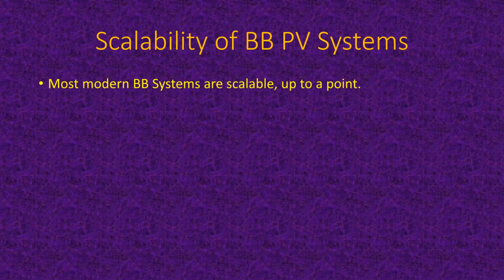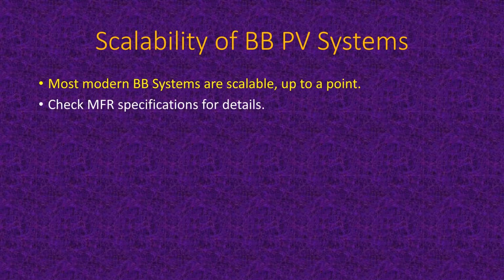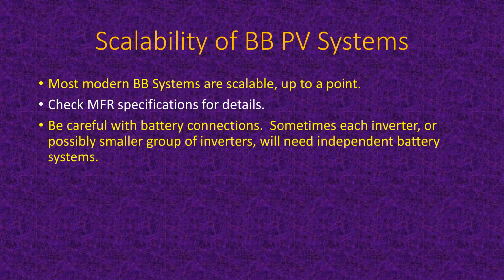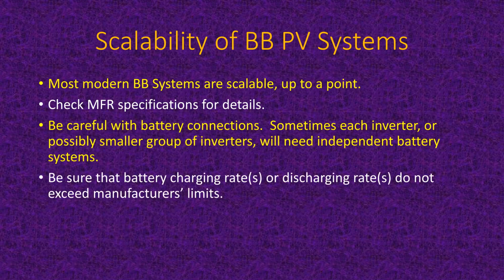Scalability. Generally, you can scale these things up. You got, say, an 8 kW inverter, 8 kW system. You can oftentimes use about 10 of them in parallel. Get yourself up to 80 kW. Need to be a little careful. Sometimes the battery systems have to, each inverter may need to have its own battery system. Okay, so you need to check the manufacturer's specs. Watch out with the battery connections. And make sure battery charging rates or discharge rates don't exceed the manufacturer's limits. It's easy to do that if you're not careful, have too much array. Then you might have way too much current for charging the batteries, and that can shorten their lifetime.